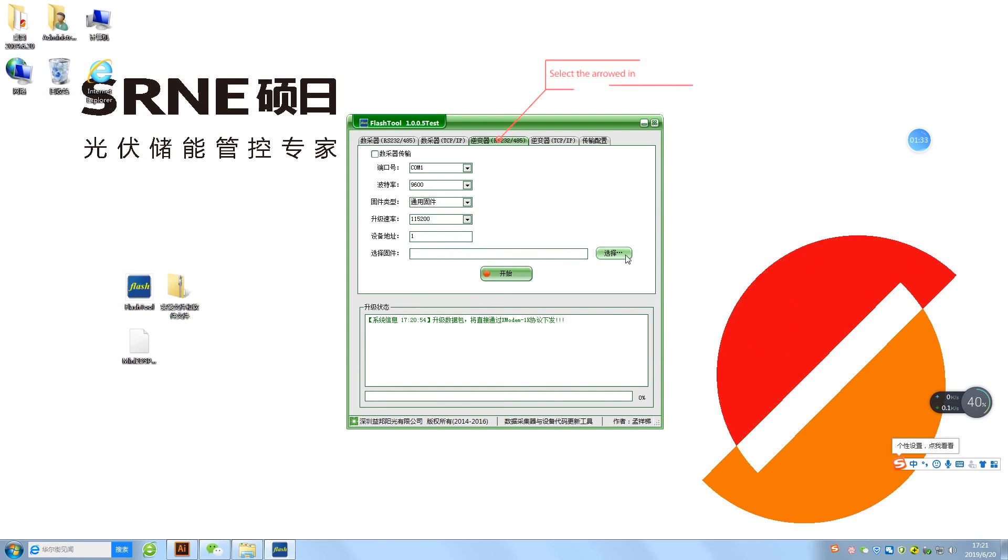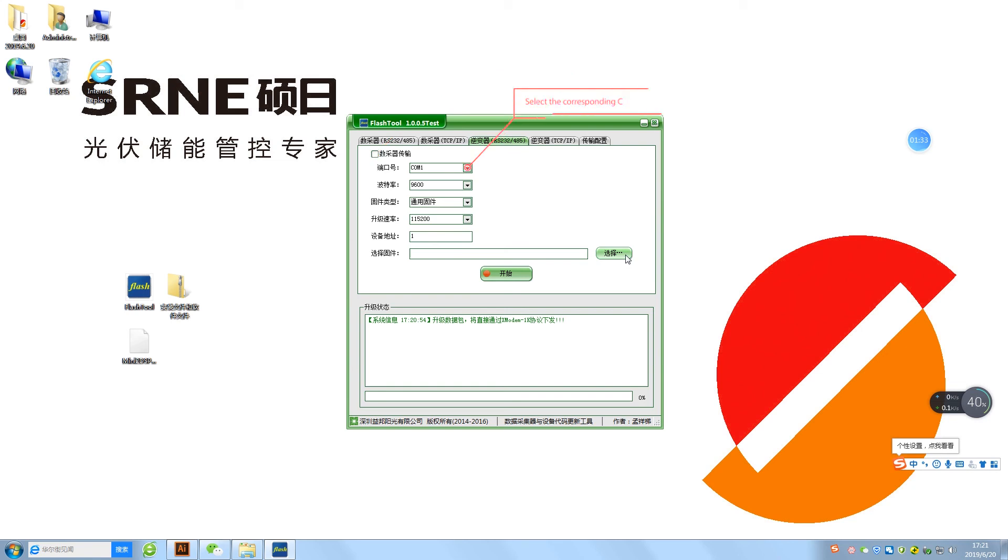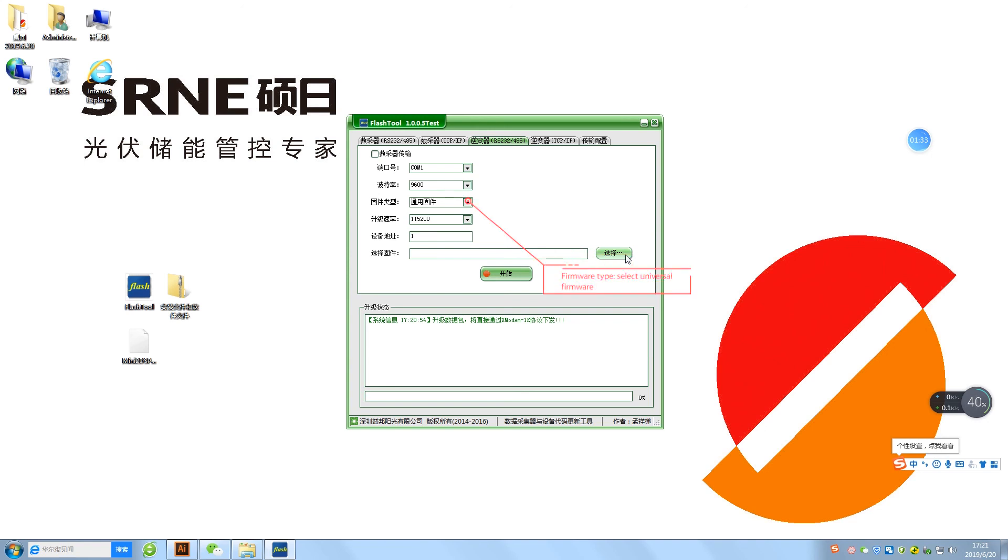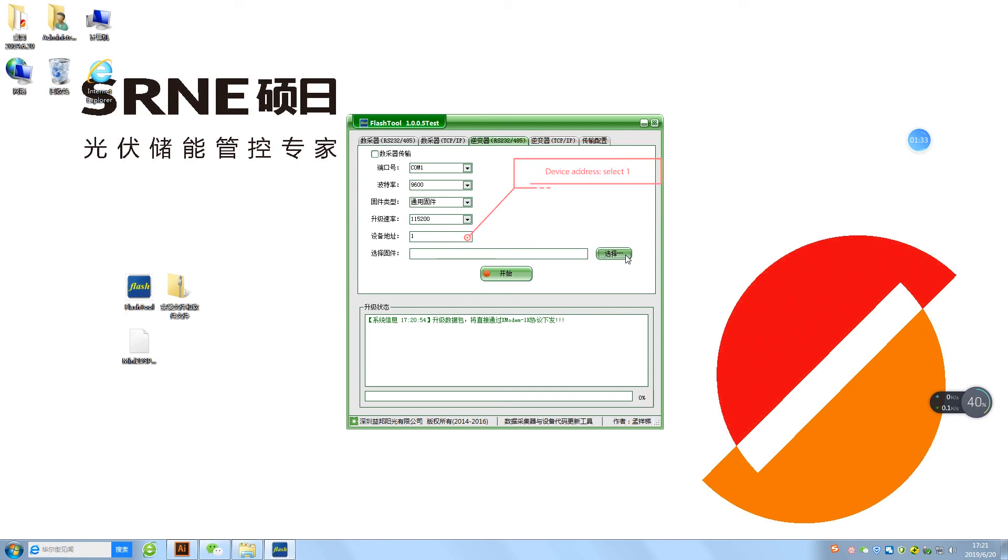Select the arrowed icon. This option is not chosen. Select the corresponding COM port. Select the baud rate 9600. Firmware type: Select Universal firmware. Upgrade rate: Select 115200. Device address: Select 1.